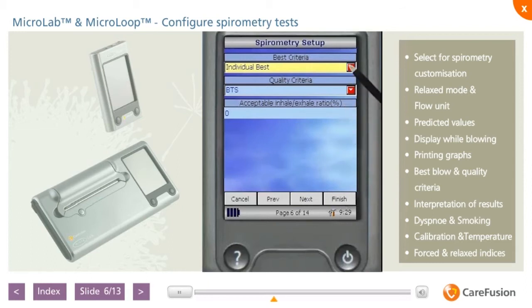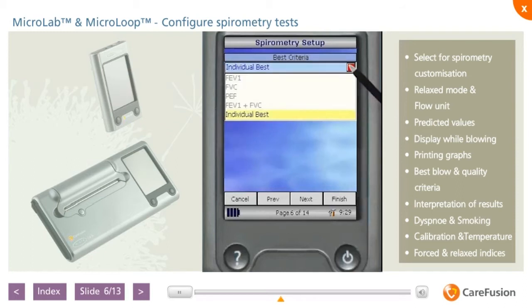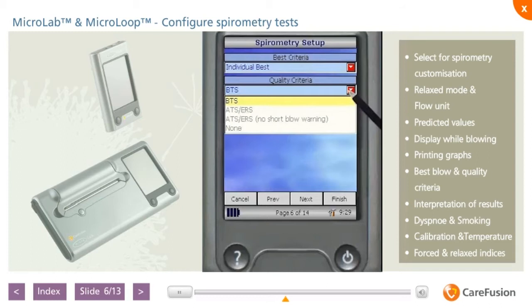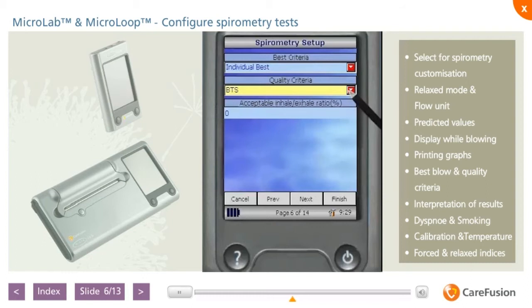The option on this screen allows selection of the best blow criteria and the quality criteria applied to the blows for reproducibility between maneuvers. The current ATS ERS 2005 standards recommend the individual best criteria are used. Quality criteria are based on national preferences and can be chosen from the BTS, the British Thoracic Society, or ATS, American Thoracic Society. The acceptable inhale-exhale criteria allow a chosen ratio, for example 50, to be selected, which enables a separate inspiratory maneuver to be performed when a patient is unable to fully inhale after exhalation. Leaving the value at 0 means no criteria has been set and the maneuver can't be performed separately from an expiratory maneuver. Select Next to proceed.